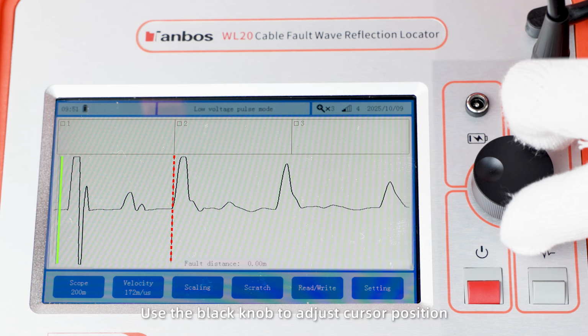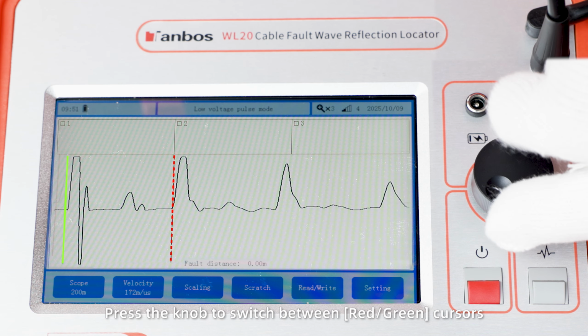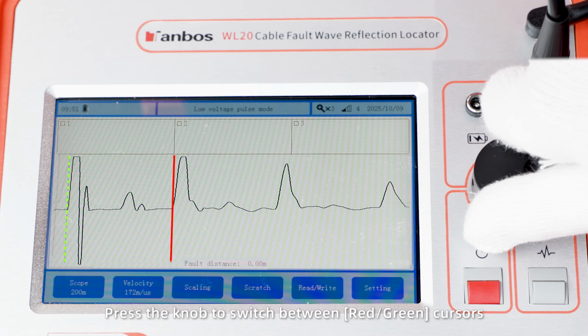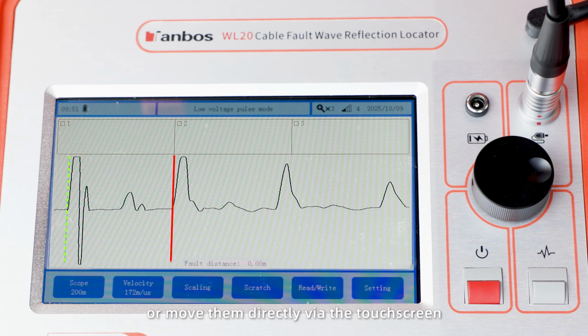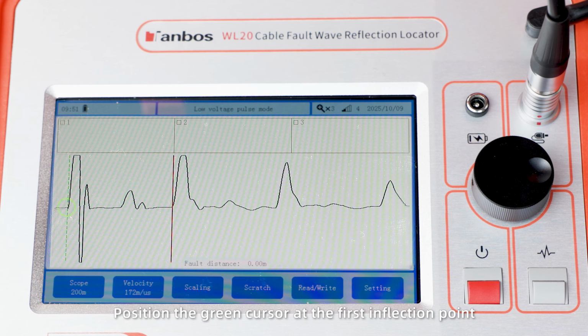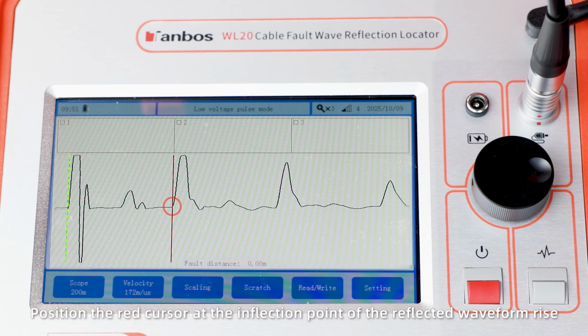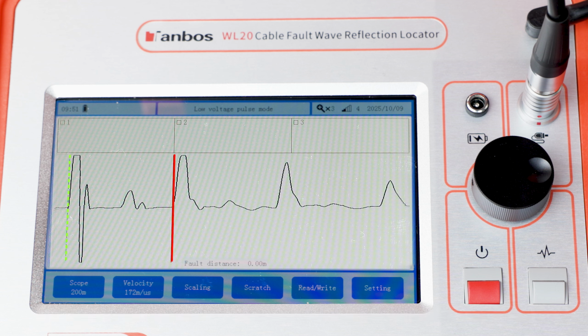Use the black knob to adjust cursor position. Press the knob to switch between red-green cursors or move them directly via the touchscreen. Position the green cursor at the first inflection point, where the initial waveform rises. Position the red cursor at the inflection point of the reflected waveform rise.